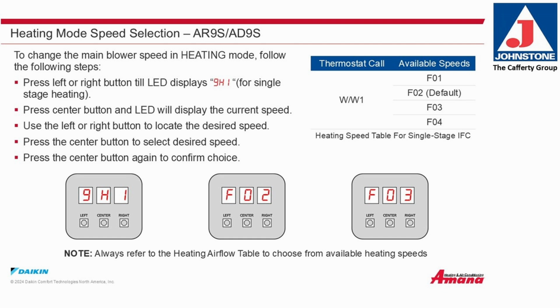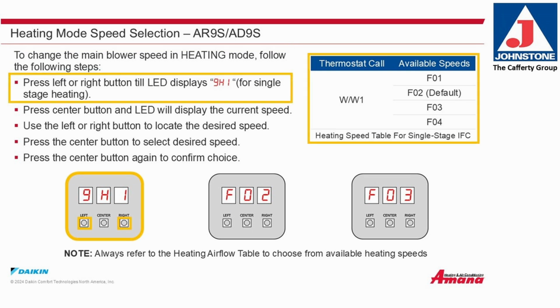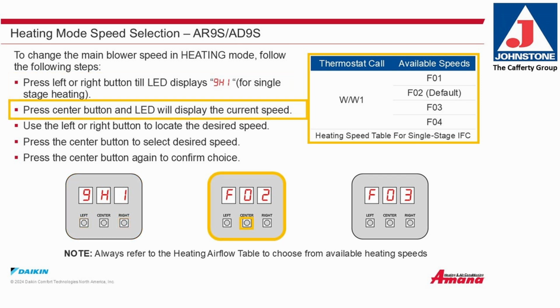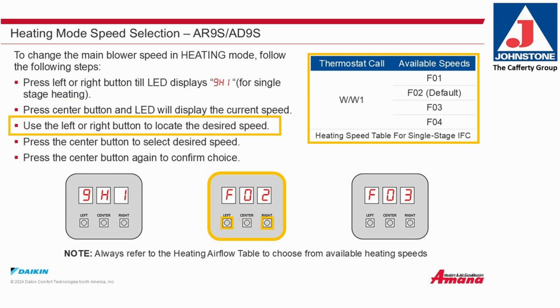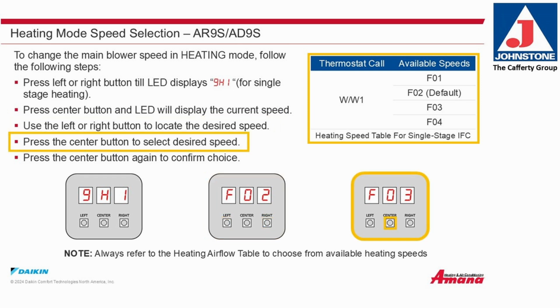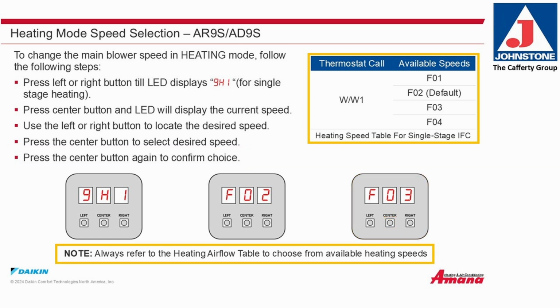Heating mode speed selection. To change the main blower speed in heating mode, follow these steps. Press the left or right button until the LED displays 9H1 for single-stage heating. Press the center button and the LED will display the current speed. Use the left or right buttons to locate the desired speed. Press the center button to select the desired speed. Press the center button again to confirm your choice. Always consult the heating airflow table to choose from available heating speeds.